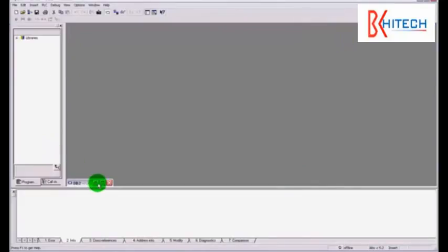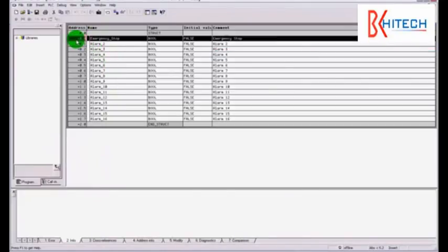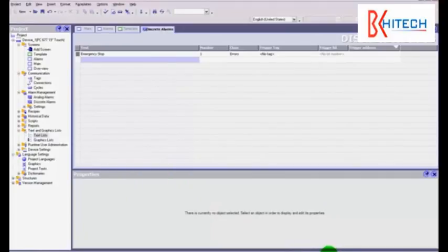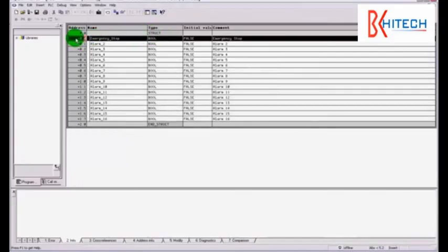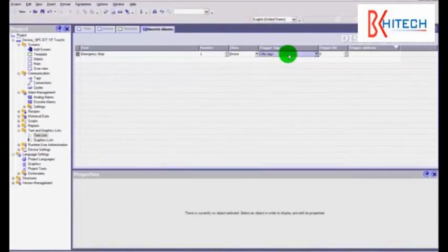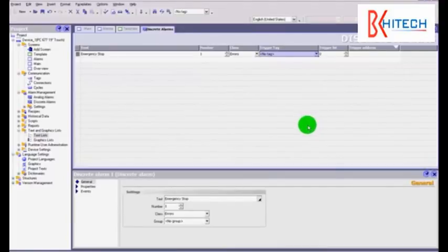And if we go back to our previous ladder and open up our DB2, this is the alarm that we're going to trigger it to. So when the PLC triggers that data block bit, that will send a message to the screen to say trigger that alarm that is connected to 0.0 in DB2. Alright, so we go back, and this is part of our trigger tag.